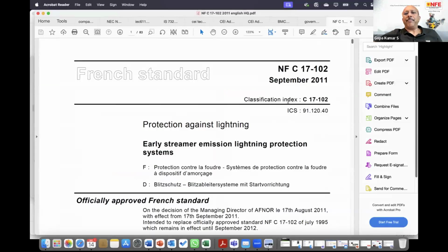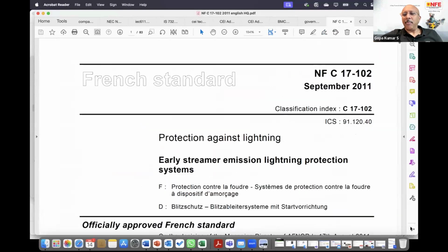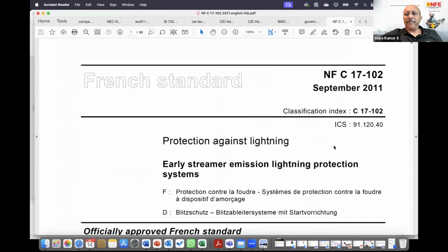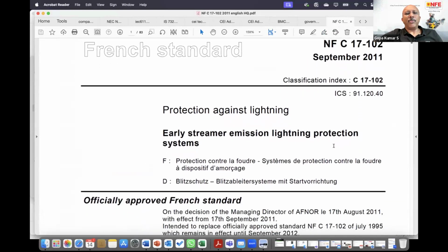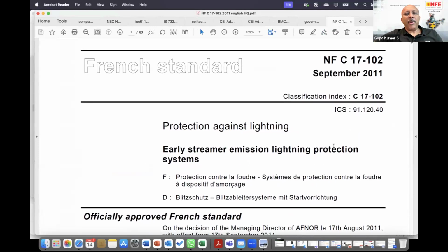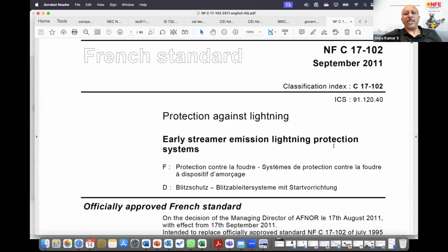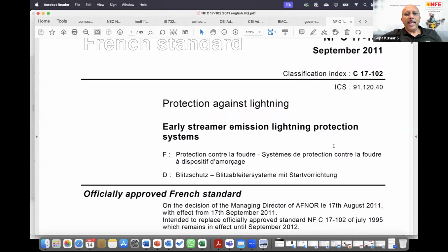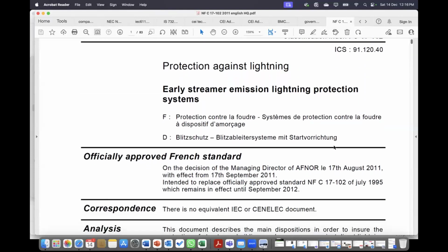Now, regarding NFC, the first answer is that every nation has buildings where lightning protection is not mandatory. Not mandatory means small houses. Nobody bothers whether lightning protection is installed or not, neither the insurance system nor the authorities. In such cases, ESE lightning protection systems as per this NFC are widely used all over the globe because nobody bothers. It is up to the user. If he has money, he can use something, and it is up to the user to decide. 99% of the installations of ESE are made for buildings where lightning protection is not mandatory. Now, the second case: larger buildings, taller buildings where lightning protection is mandatory.